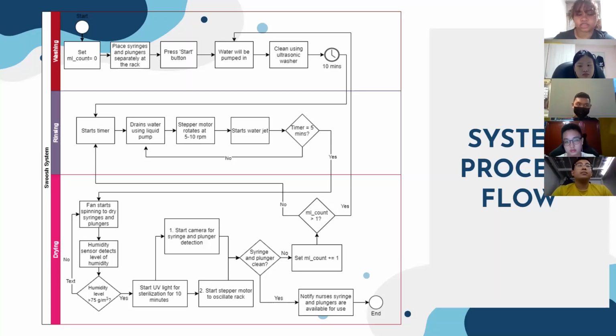Afterwards, the drying phase comes in, where the fan will start to spin to dry the syringes and plungers, and the humidity sensor will then come in to detect the level of humidity. We detect whether the syringes are dry or not using our humidity sensor. If the humidity level is less than 70 gram per meter cube or 75 gram per meter cube, it will be deemed as clean. This is where the sterilization comes in for about 10 minutes. Afterwards, 2 steps will be done concurrently, which are starting the camera for syringe and plunger detection, and starting the stepper motor to oscillate the rack.